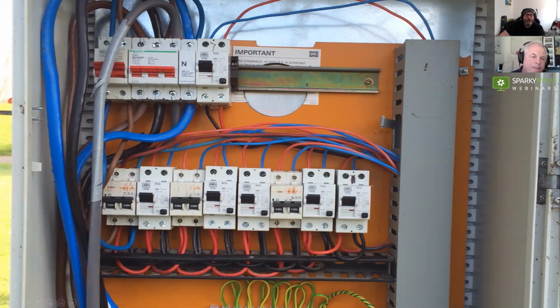So to conclude, then, we've got no necessary overcurrent protection for this cable here. Because obviously you can see this large cable's probably got overcurrent protection from its supply, but then this smaller cable coming out of the top has no overcurrent protection. We've changed the size of the cable. And we know in the regulations, whenever the current carrying capacity of the conductor changes, whether it be the cable size or even the environment that it's in, there should be an overcurrent protective device installed. That's under chapter 43. So there should be something there. Then that comes under here, and then that goes down to here.